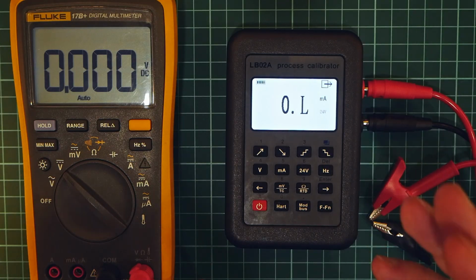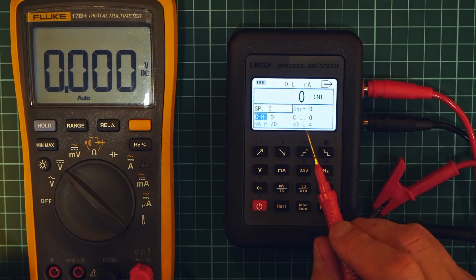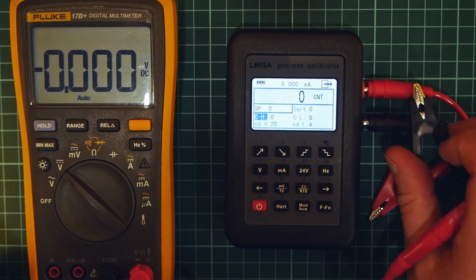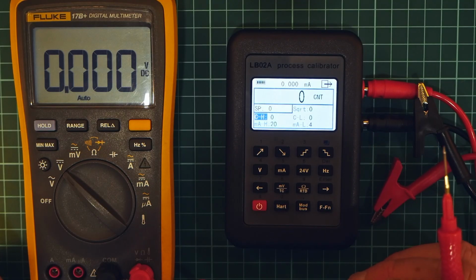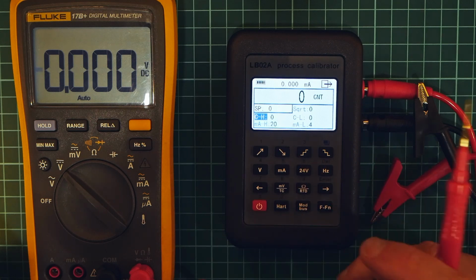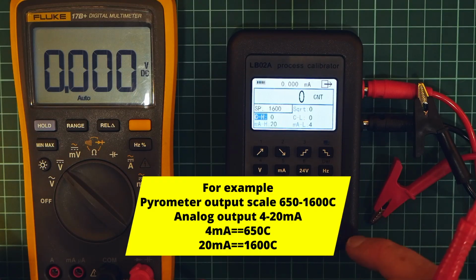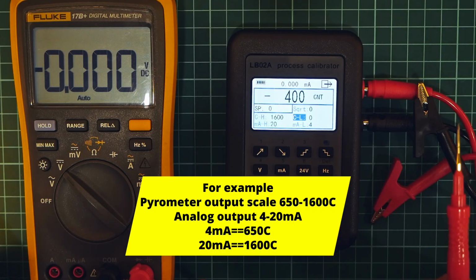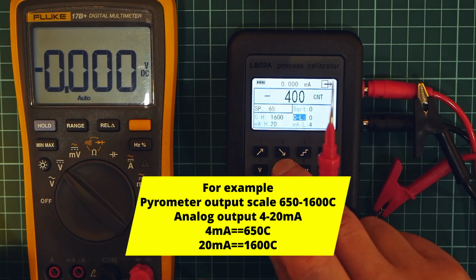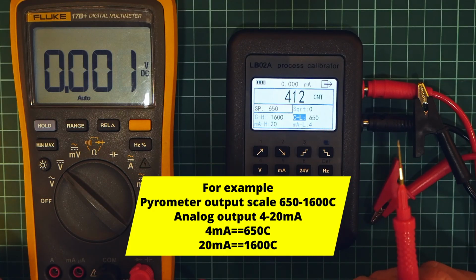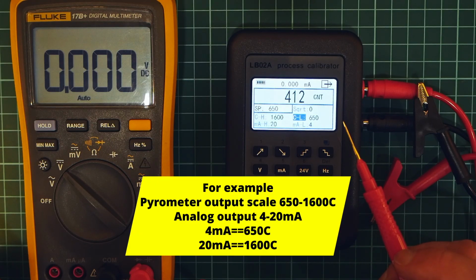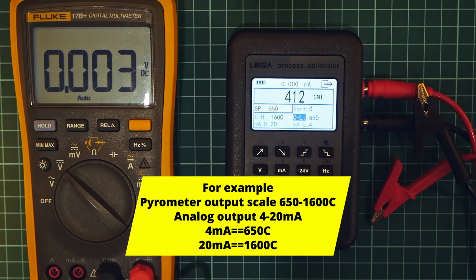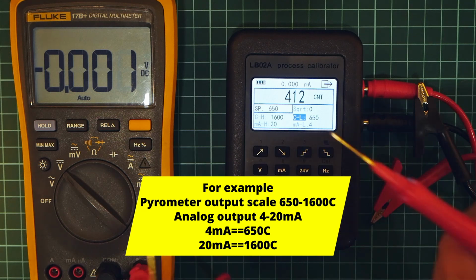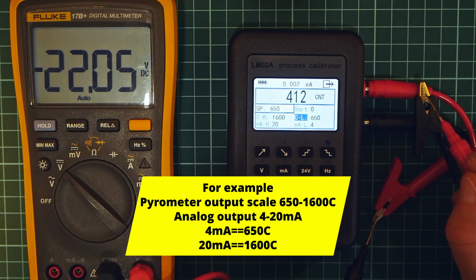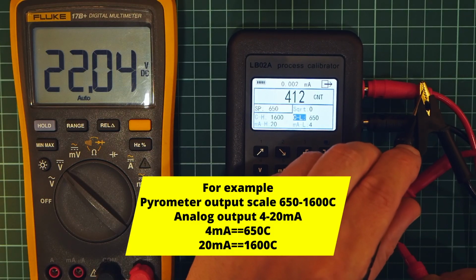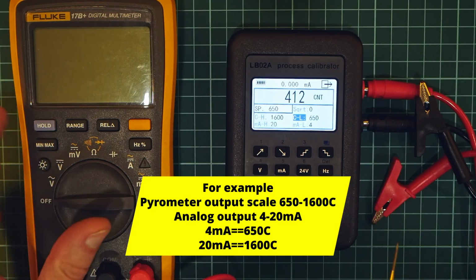So we can output 24 volts, and if we go to function, again, same story. We enter, let's say, we will connect sensor from 4 to 20 milliamps, and we will say, I don't know, when 20 milliamps, value should be 1600, yes, and when 4 milliamperes, maybe value could be 650. So these are actual values of the pyrometer I'm working with. But when we measure actually what we have here, we don't have 24 volts on these leads, we only have 22.